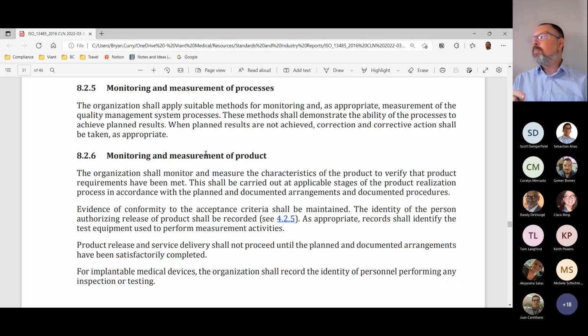So for example, if one of your requirements is a visual inspection of a component, and after you put the entire assembly together, you can't even see that component because it's buried down inside the assembly, then the final packaging and sterile lot release is not the appropriate place for you to be attempting to do that inspection. You should be doing it at the point in the manufacturing process where it's most relevant for you to perform that inspection. So when they talk about applicable stages of the product realization process, that's what they're talking about. You want to put the inspection closest to the point of manufacturing that you can, where it is relevant and applicable for you to perform that inspection.